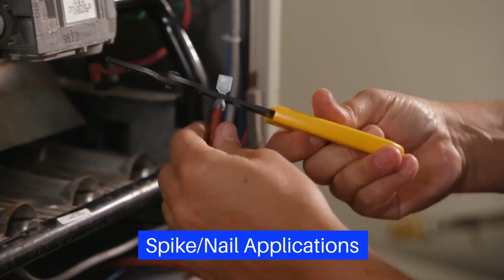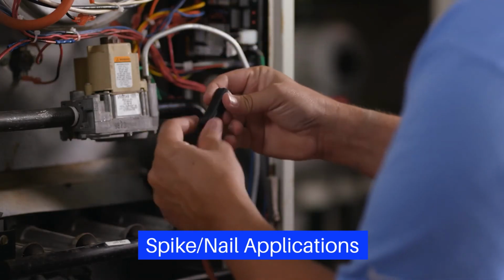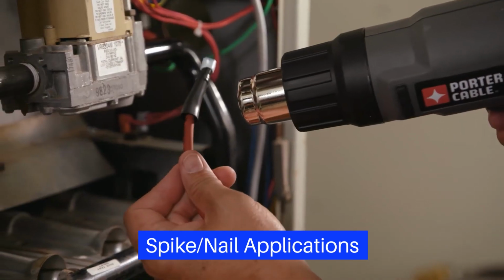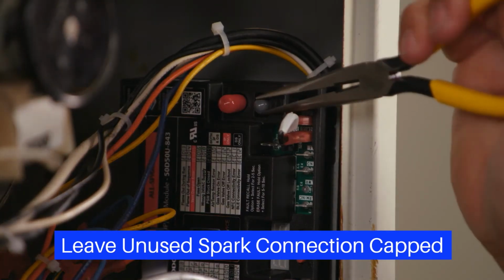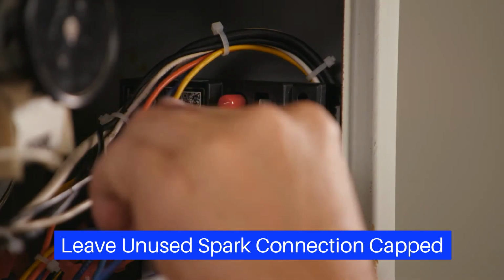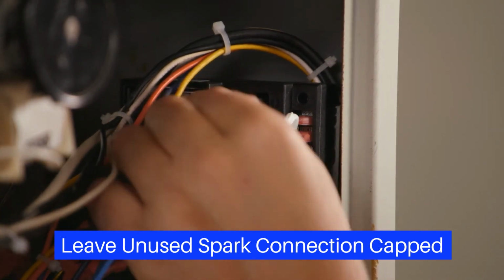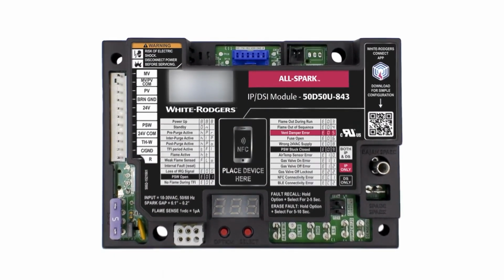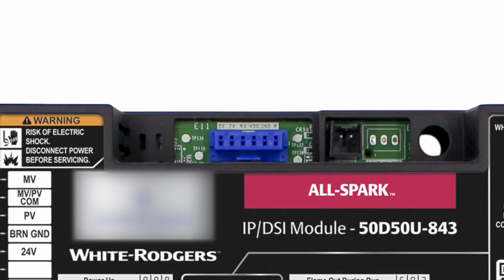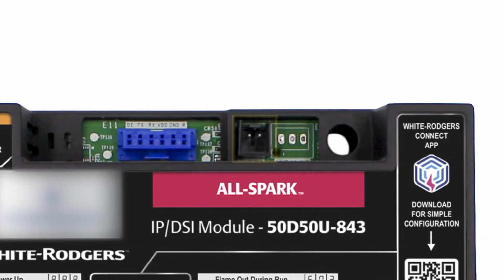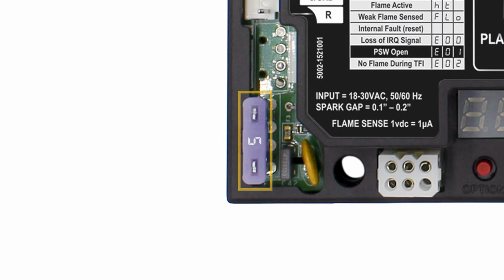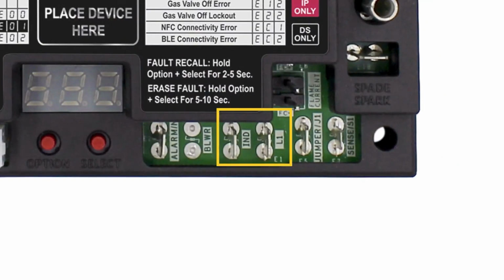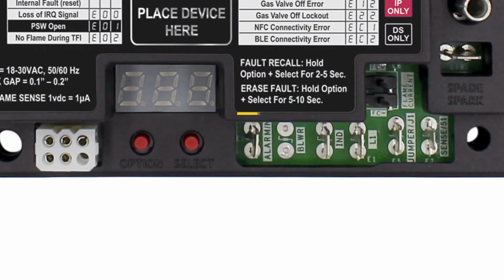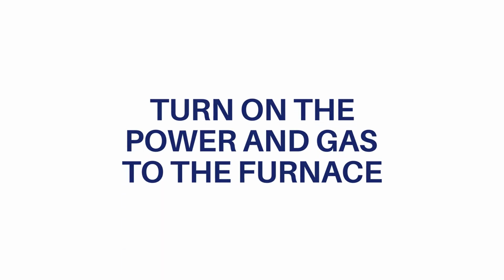Use the provided shrink-wrap sleeve to prevent the spark from escaping from between the wire and the adapter connection. For this application, the 1/4-inch spade is used. Remove the lower gray cap and plug in the spark wire. This control also features a Bluetooth connector, an air temperature sensor connector, replaceable fuse, a 120 or 240 volt inducer motor input and output, and a 24-volt alarm output. The system is now ready to be powered on.